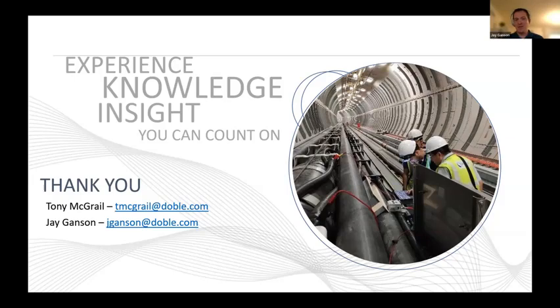There's specific language in the infrastructure bills that have come out talking about monitoring and cable monitoring. So I think there's more acceptance of looking at this, but probably one of the biggest drivers is that the general cost of putting in underground transmission is pretty high. When you look at it as a ratio of monitoring versus the infrastructure or replacement cost, it looks more attractive than if it was applied to an overhead transmission project. Yeah, the cost of underground transmission is really high. The average cost of overhead is 390K per mile, whereas underground can be up to about 2 million a mile, and that is without any of the NIMBY considerations or permitting, which can also add lots of cost and time to a project.